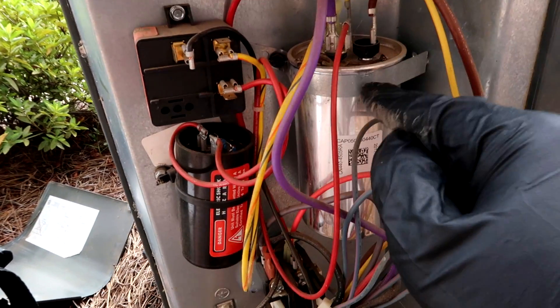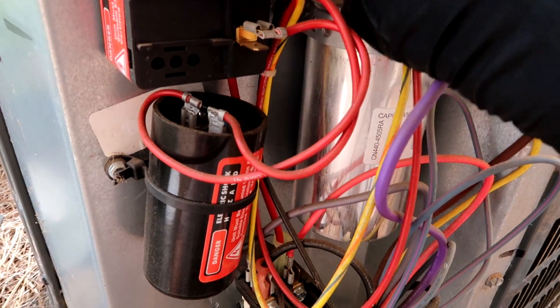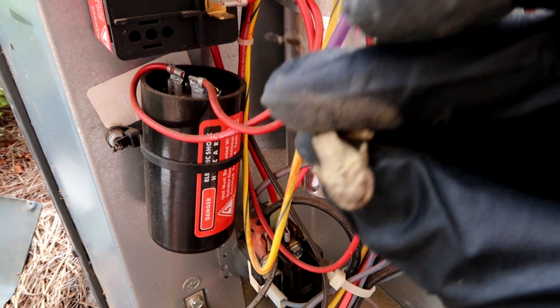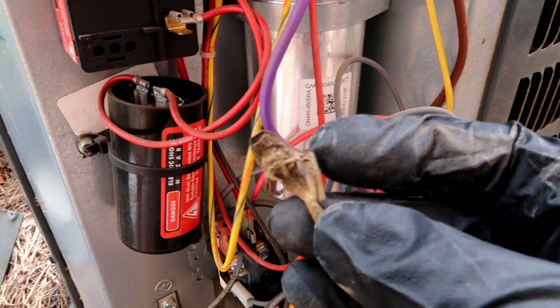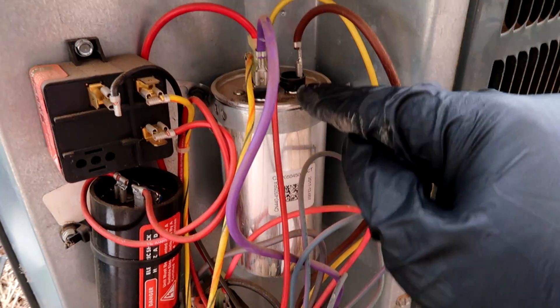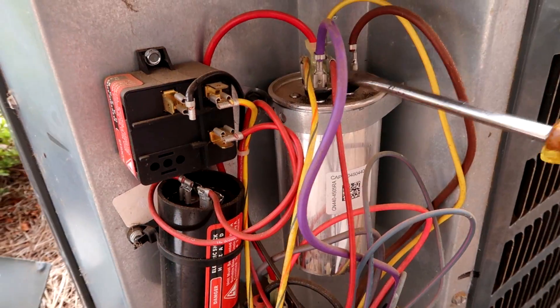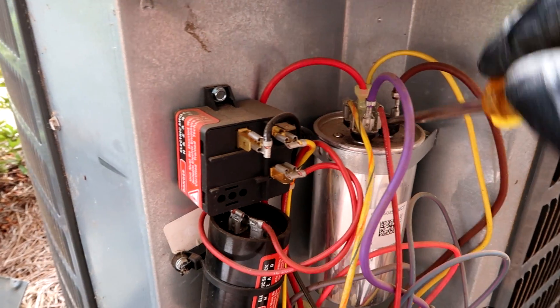A little relay and the capacitor. Look — a little dead frog on there. I'm sure that didn't help anything. Sorry little buddy, you crawled in the wrong unit. At least you could have died on a Trane, big dog, not a Goodman. All right, we'll check the capacitor here — discharge the cap, get all the energy out of it.